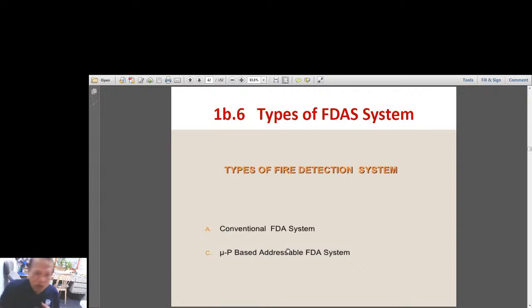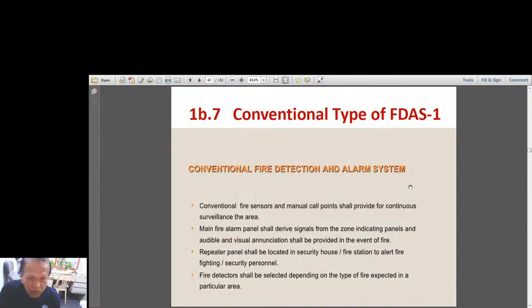So you cannot use components in a conventional system in an addressable system, or similarly, you cannot use components in an addressable type, like detectors and output devices, in a conventional system. They will not work. Okay, conventional. So between the conventional and the addressable type, they are just simply the same, except that, like I said, the addressable type has a computer, and this one doesn't have a computer. This conventional, of course, is a lot cheaper than the addressable type.